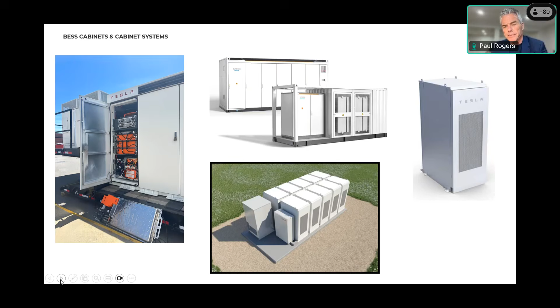The separation distances, if they're going to be 6 inches, how did they get that 6 inches? Did they use heat flux analysis from number one versus number two? That new system has to have 9540, 9540A. All of that needs to come in there to make sure that when they do go augmented, if that system were to fail, it doesn't propagate to the original systems that are already up and running. So all of that needs to be incorporated, and they should get a permitting review on that too. So just keep that in mind, that we will see this down the road. Next.